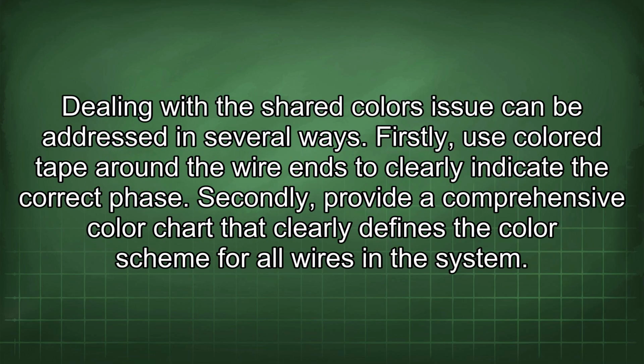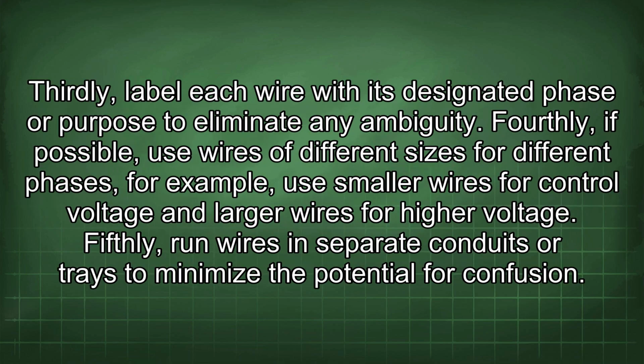Dealing with the shared colors issue can be addressed in several ways. Firstly, use colored tape around the wire ends to clearly indicate the correct phase. Secondly, provide a comprehensive color chart that clearly defines the color scheme for all wires in the system. Thirdly, label each wire with its designated phase or purpose to eliminate any ambiguity.